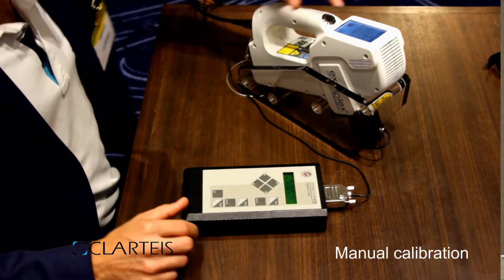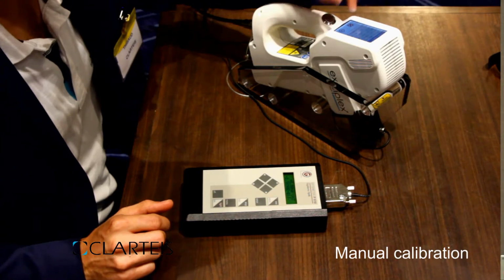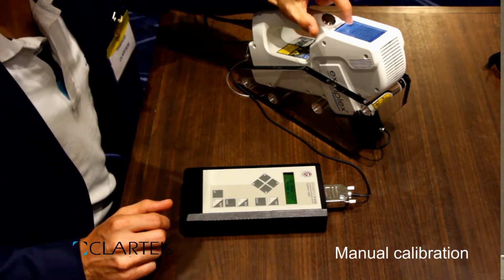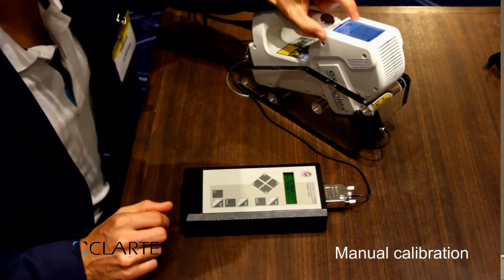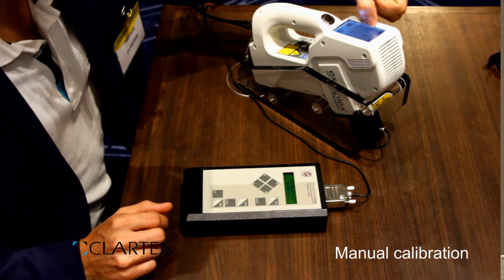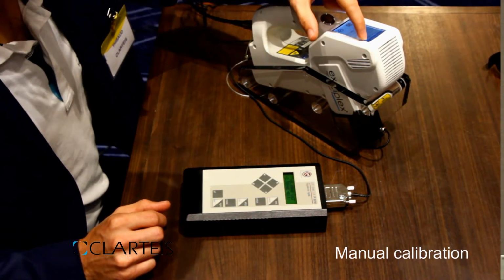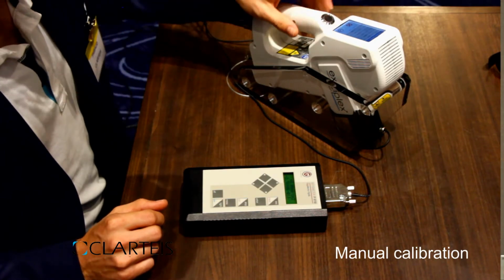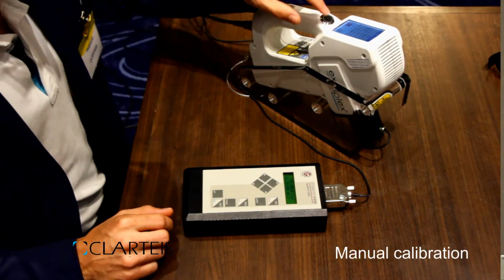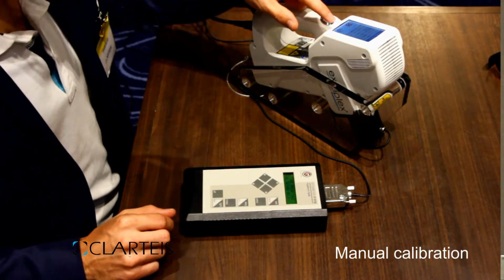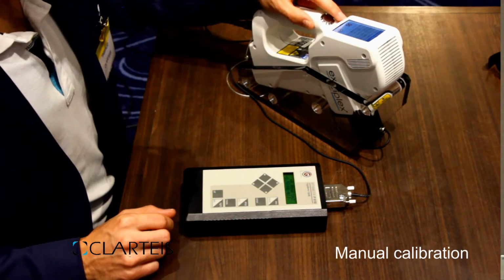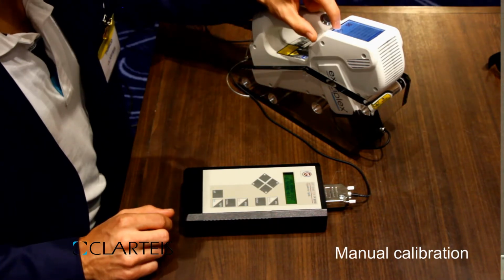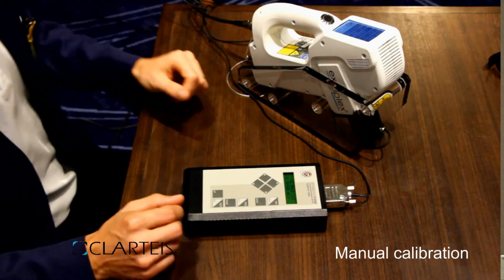Before pressing OK, just make sure that the values are good and the error is below 2%. You will have to refer the old value and the new value into the form. If calibration is OK, you can valid, otherwise you just press no. So you just performed an Exciplex calibration.